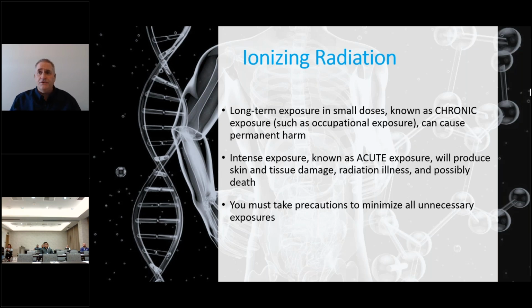And we're usually talking in millisecond time frames. So exposures are incredibly short. They're very directed. And in general, if you're not standing there exposing yourself, you will not have much, if any, exposure from X-ray radiation. The other neat thing about that is you can take X-rays all day long on a piece of equipment, and the minute you turn it off, you can go service that without any radioactivity.